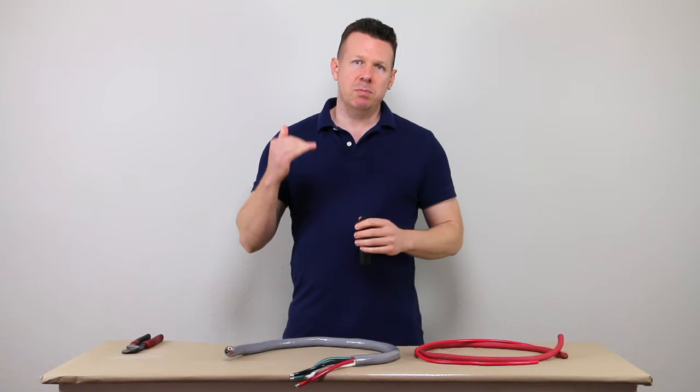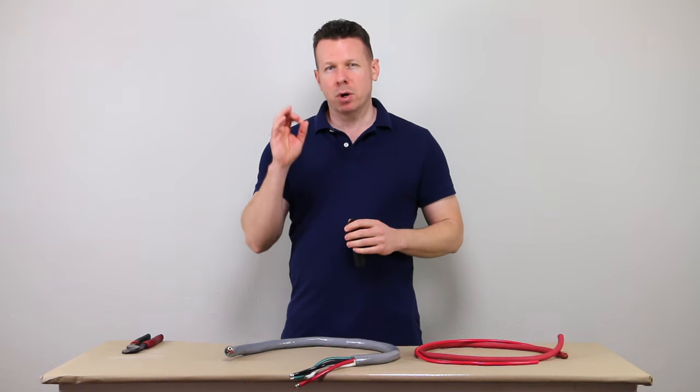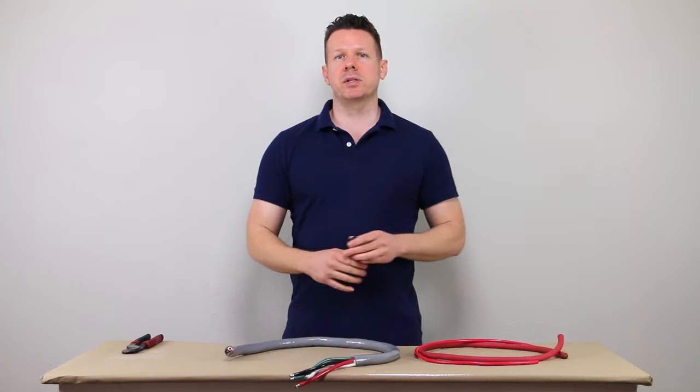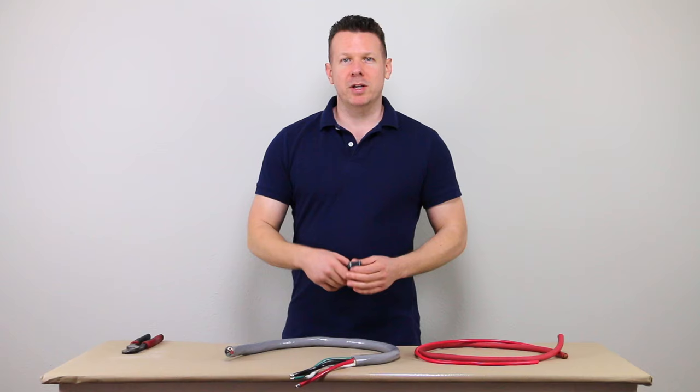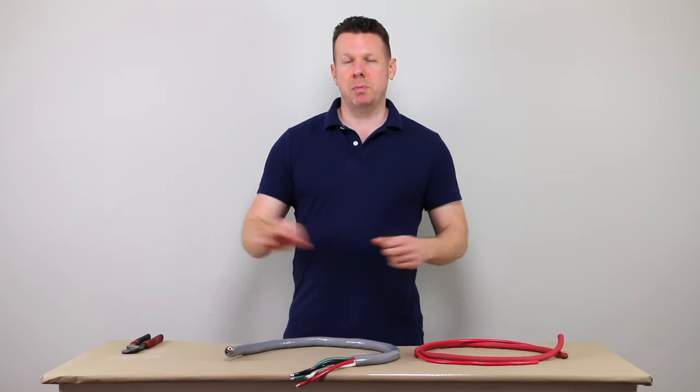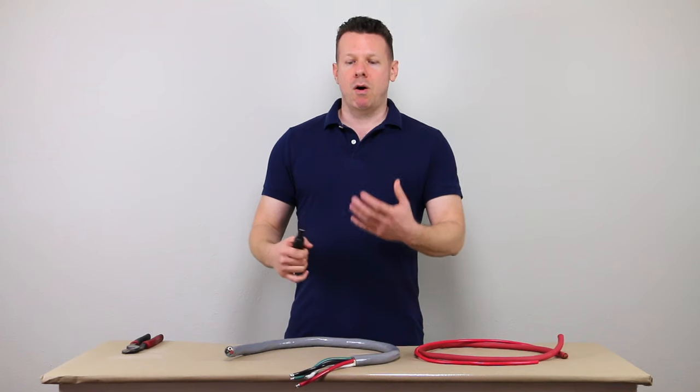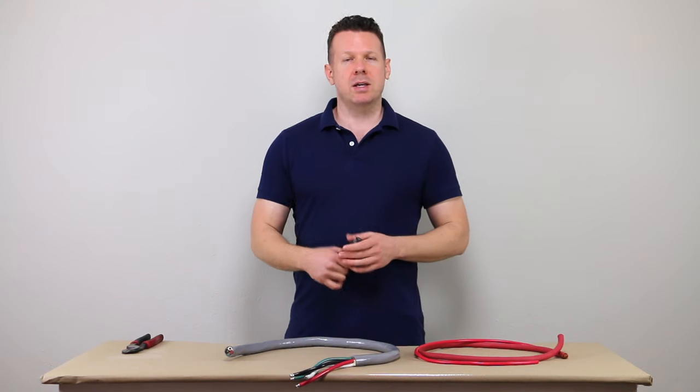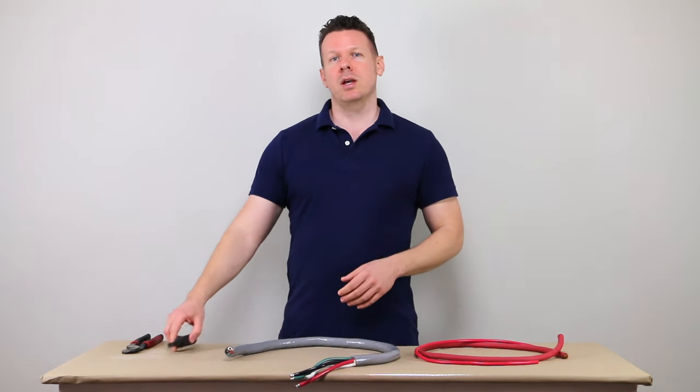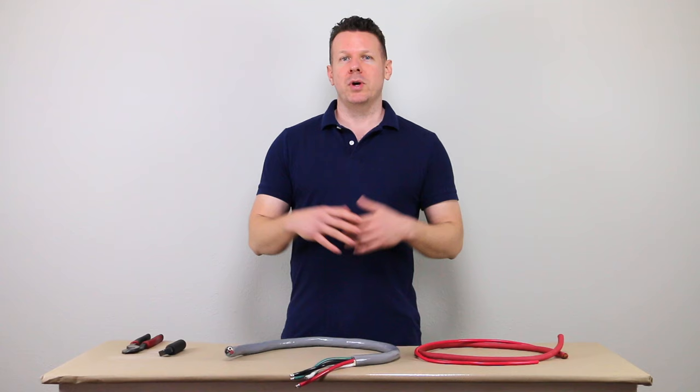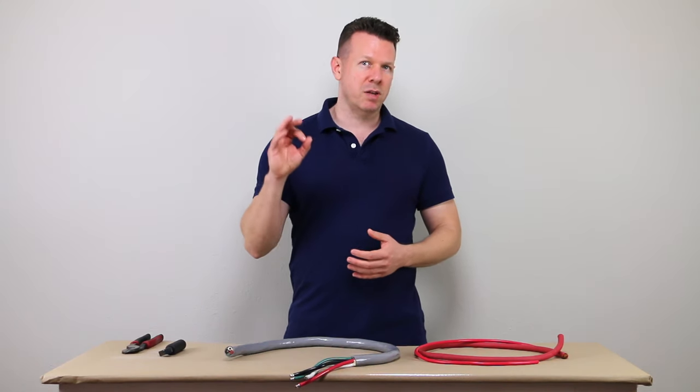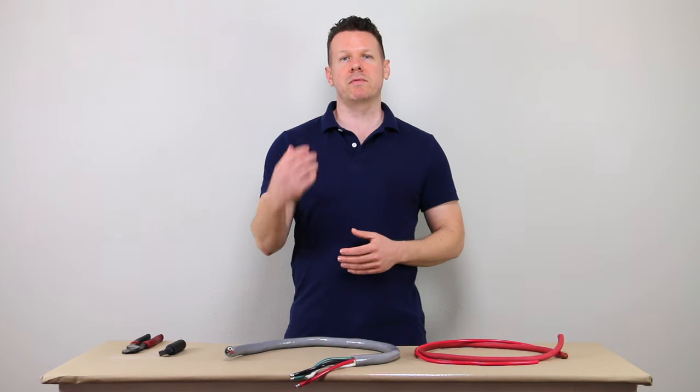It has a blade depth that you can micro adjust and set for the exact thickness of your cable insulation. Make sure you don't cut into those inner conductors. And if you're stripping a lot of cables with the same jacket, you can do it really quickly without worrying about damaging those inner conductors. So it's definitely a tool that gives you precision and speed if you're doing a lot of cable stripping.